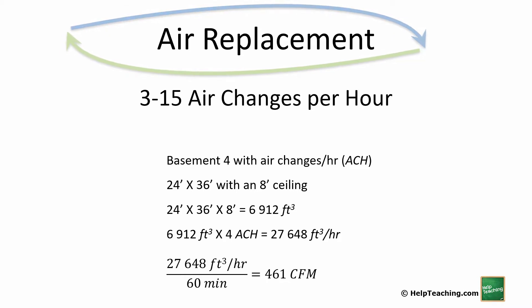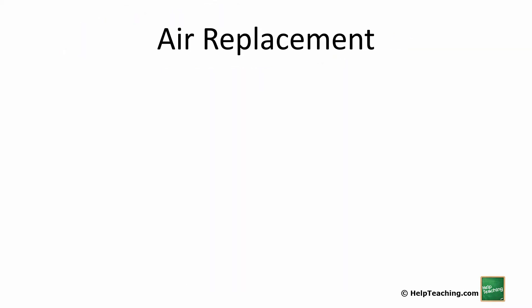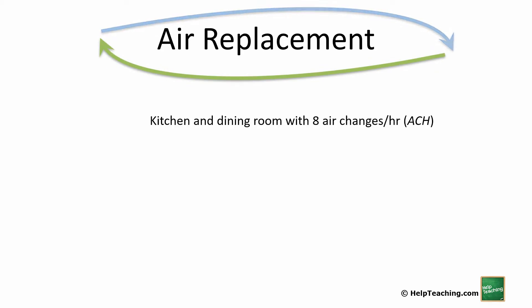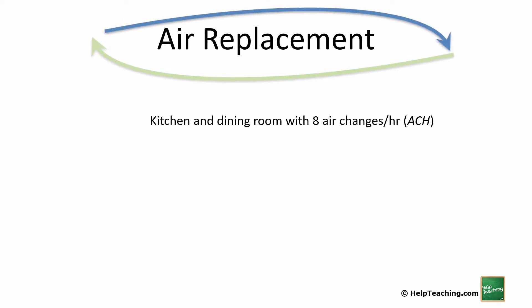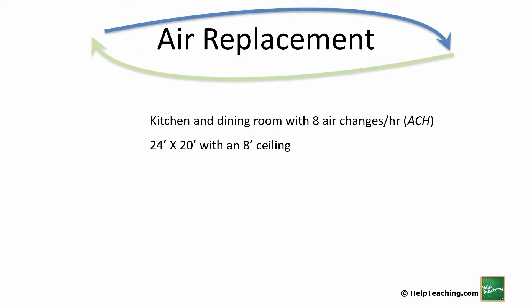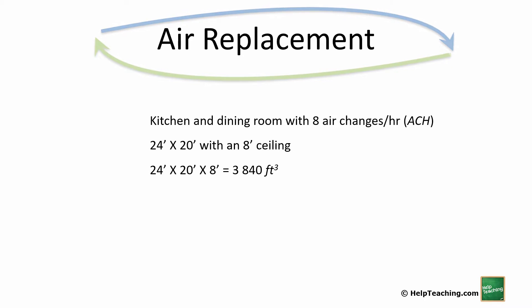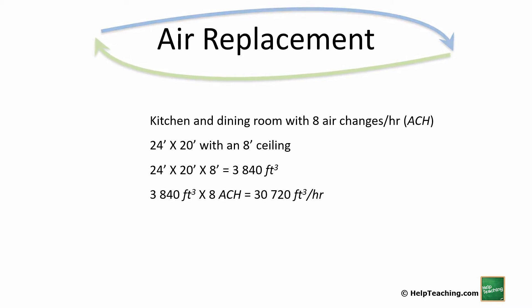Now let's look at the kitchen and dining room with 8 air changes per hour. With cooking smells and more moisture being generated, it's more important that we turn that air over on a more regular basis. This area is 24 by 20 feet with an 8-foot ceiling, giving a volume of 3,840 cubic feet. Multiplying by 8 for air changes per hour gives us 30,720 cubic feet per hour. Dividing by 60 gives us 512 cubic feet per minute.